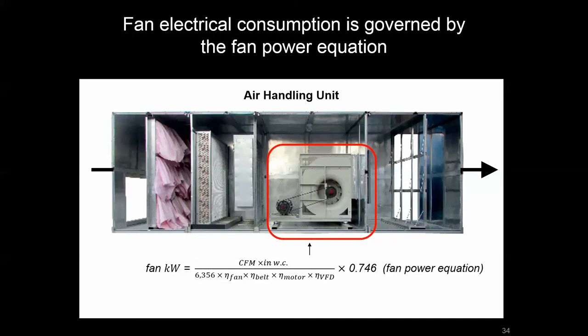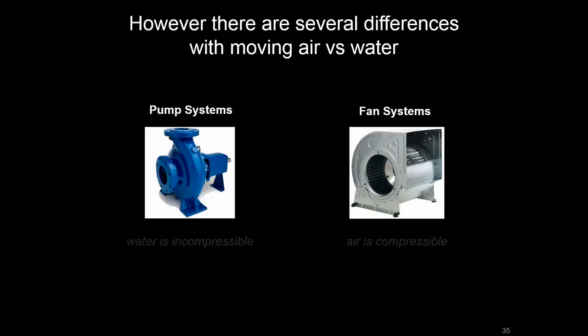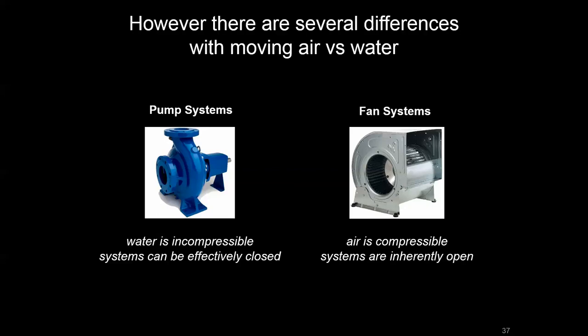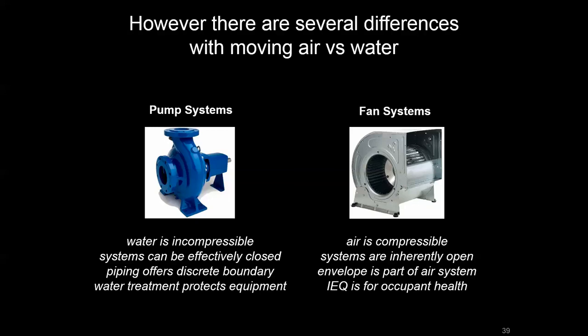On the airside, the fan has a similar electrical load story to the pump, and we'll cover the fan equation in the next video. But it's worth pausing on the key differences between these systems. Water on the pumping side is incompressible, whereas air being a vapor is compressible, which changes the dynamics of how air moves through a fan system. With pumping systems, we essentially have a closed loop with no direct interaction with the atmosphere. Fan systems are inherently open — while you have the piping infrastructure as a discrete boundary, the building envelope will always have some leakage, exfiltration, or infiltration, so the building envelope must be considered part of the air system.